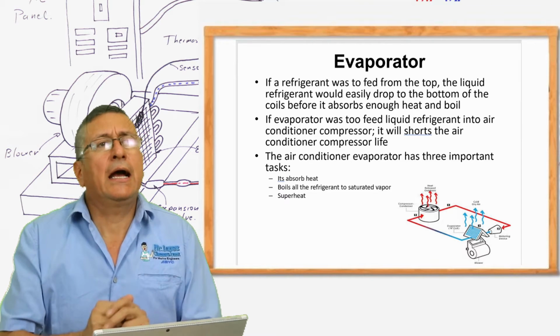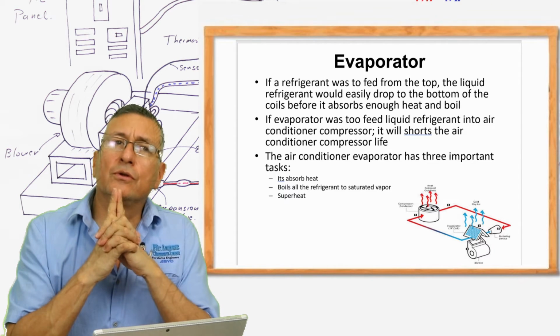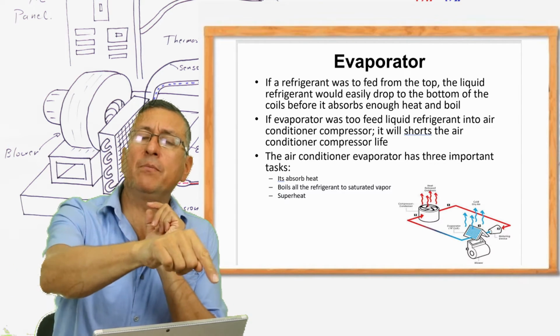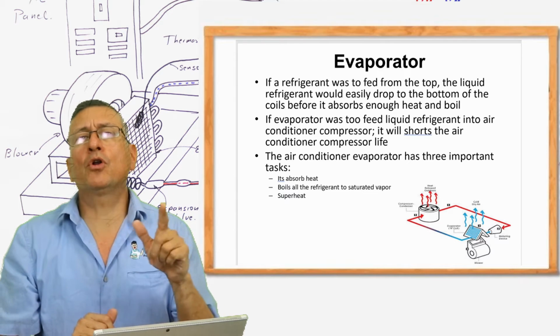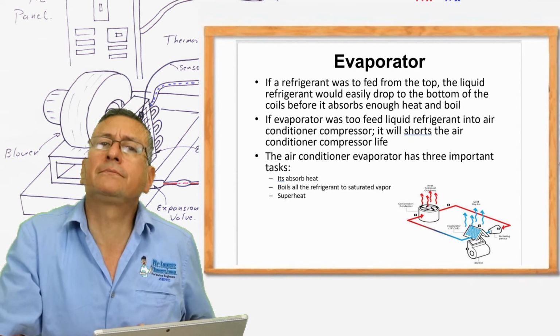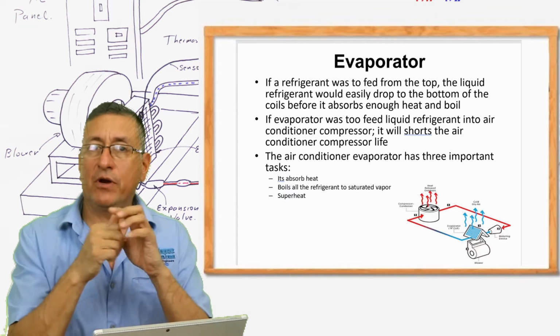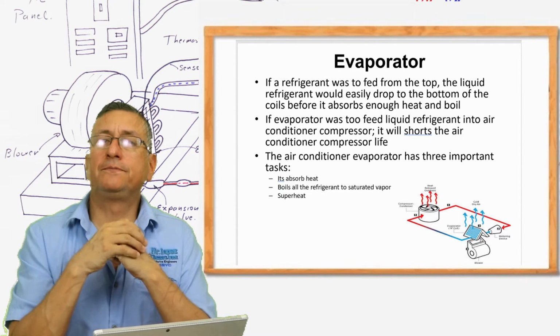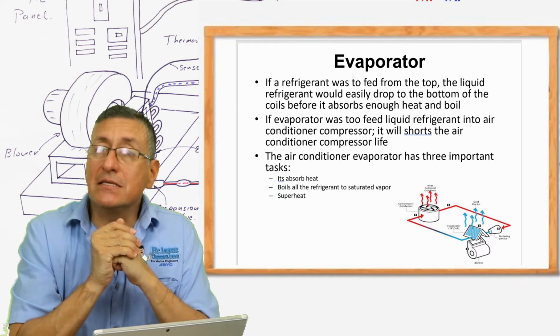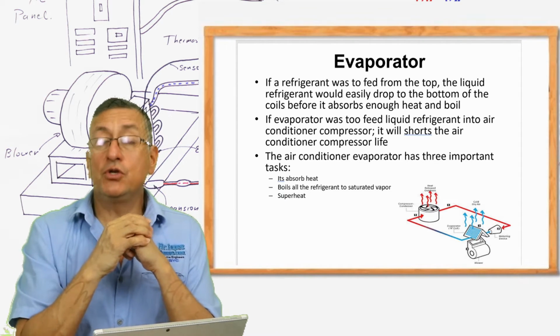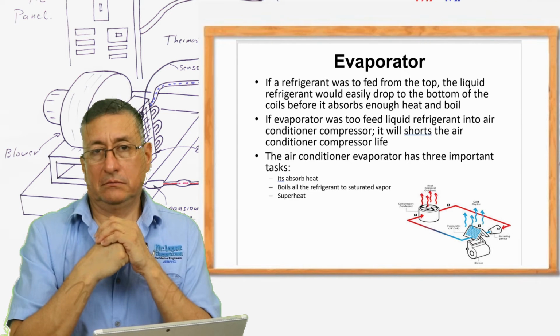And I have a $1 million question. Can I install more than one evaporator with one compressor in the bilge of my boat? Can I connect more than one evaporator with one compressor? The answer is yes, but that number of evaporators should be calculated.